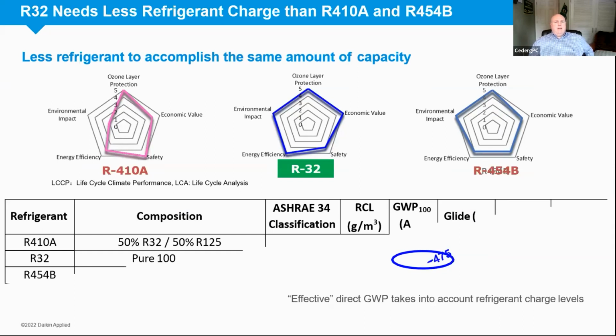I wish we could show that, because it does show you the GWP of R410A, and I can't remember off the top of my head. But one of the reasons we moved to R32 is it has a GWP of about 675. It is a very efficient refrigerant, in fact about 3 to 5% more efficient. So although it's classified as 675 GWP, the actual effective GWP is closer to 475 just due to its efficiency.